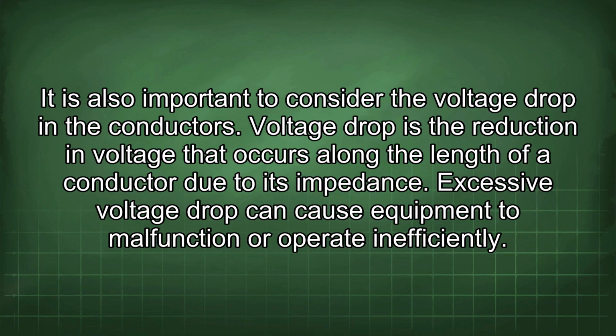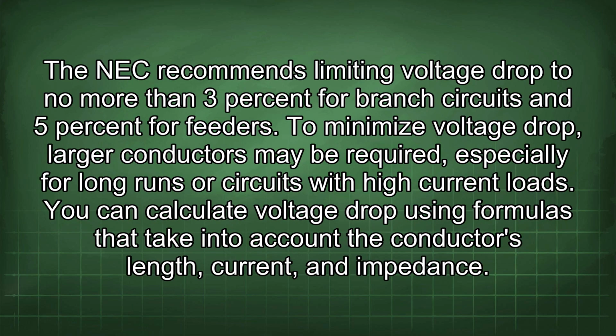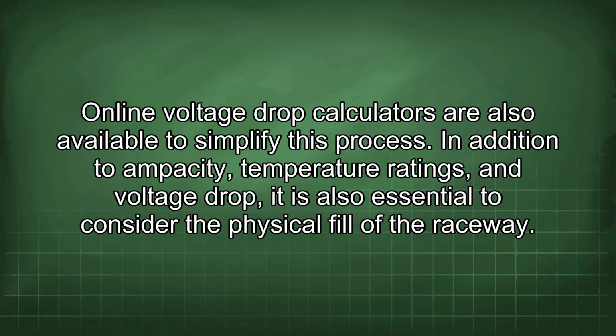It is also important to consider the voltage drop in the conductors. Voltage drop is the reduction in voltage that occurs along the length of a conductor due to its impedance. Excessive voltage drop can cause equipment to malfunction or operate inefficiently. The NEC recommends limiting voltage drop to no more than 3% for branch circuits and 5% for feeders. To minimize voltage drop, larger conductors may be required, especially for long runs or circuits with high current loads. You can calculate voltage drop using formulas that take into account the conductor's length, current, and impedance. Online voltage drop calculators are also available to simplify this process.